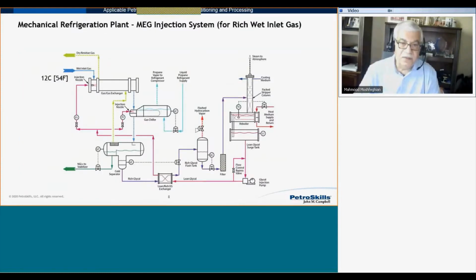So let's discuss this process flow diagram, which is for a mechanical refrigeration plant with MEG injection to inhibit hydrate formation. This is for a rich, wet inlet gas. By rich, I mean containing a good amount of NGL, and by wet, I'm referring to being saturated with water vapor. So the objective is to take the feed gas with known temperature, pressure, composition and flow rate, cool it down, and remove the heavy components from this natural gas to meet a sales gas dew point temperature of 5 degrees Fahrenheit or minus 15 degrees Celsius at a pressure of, say, 7,500 kilopascal or 1,088 psi.